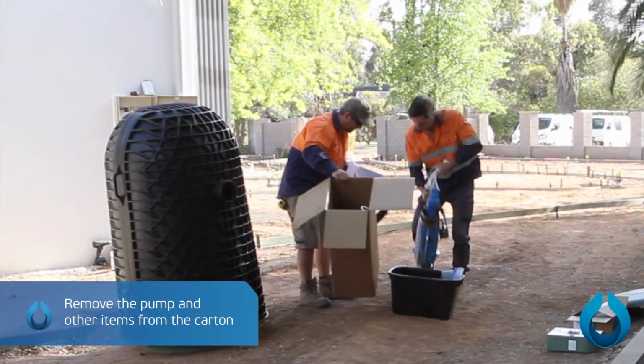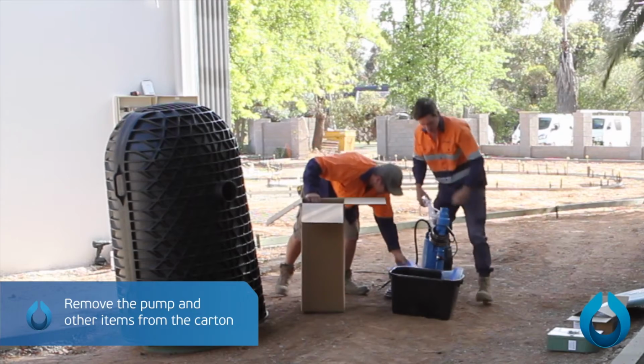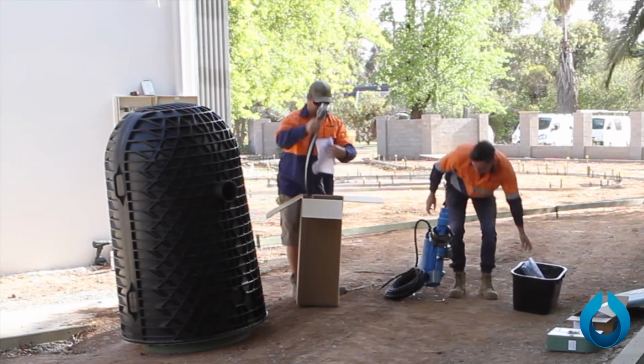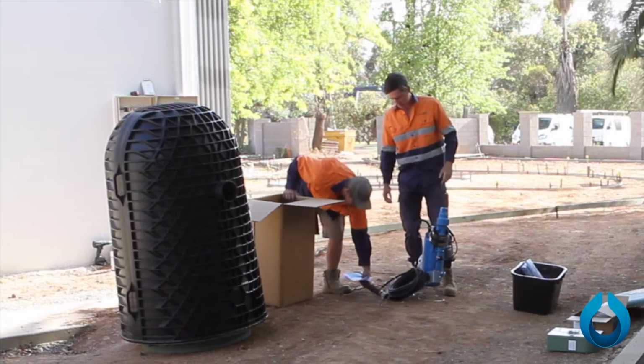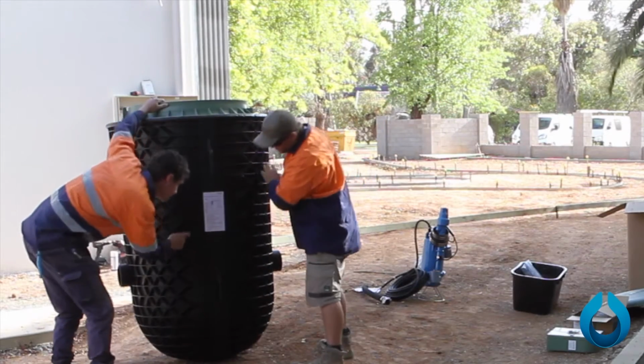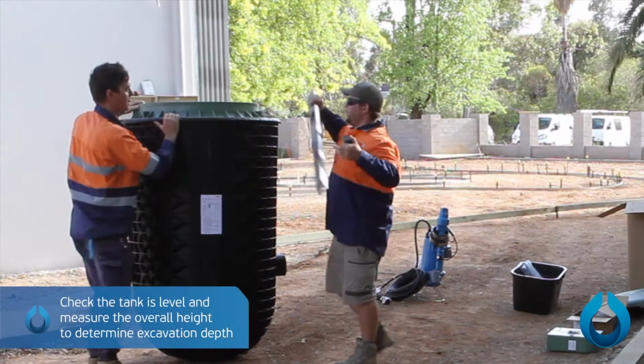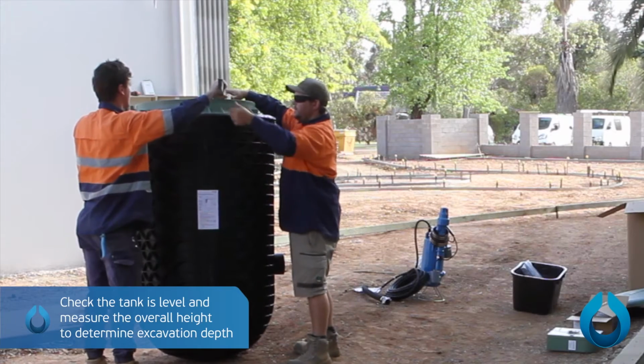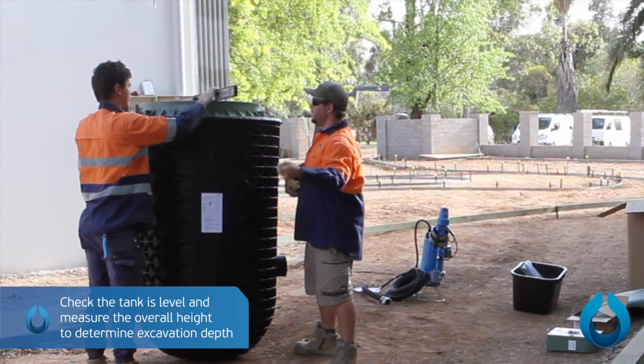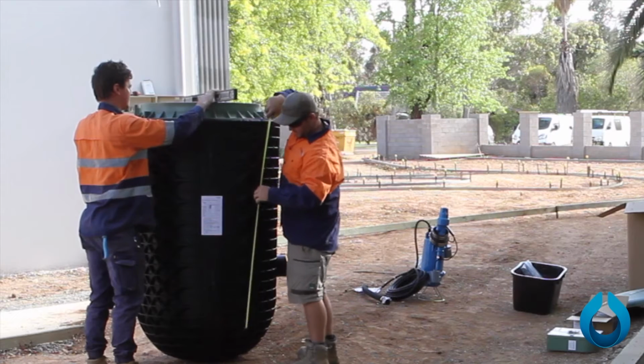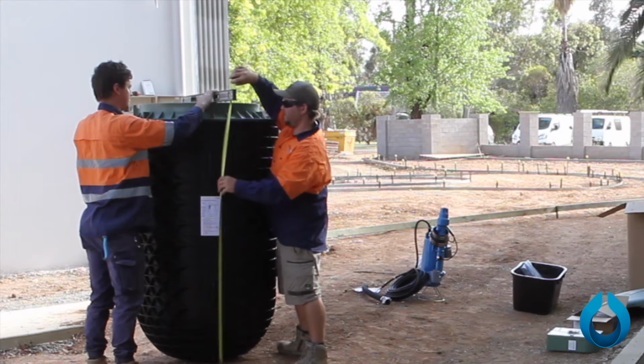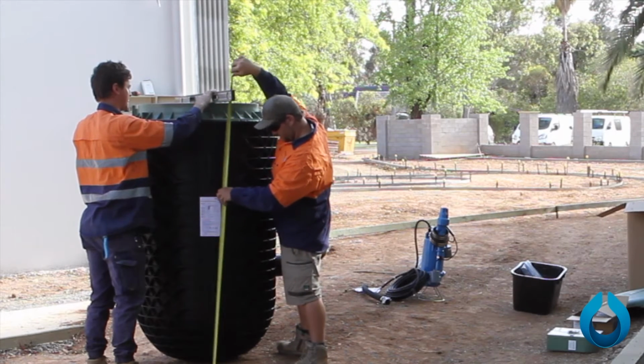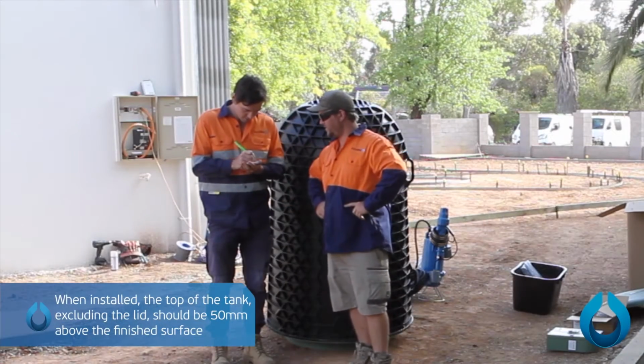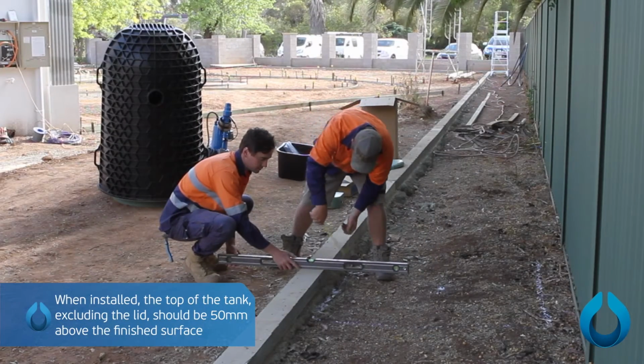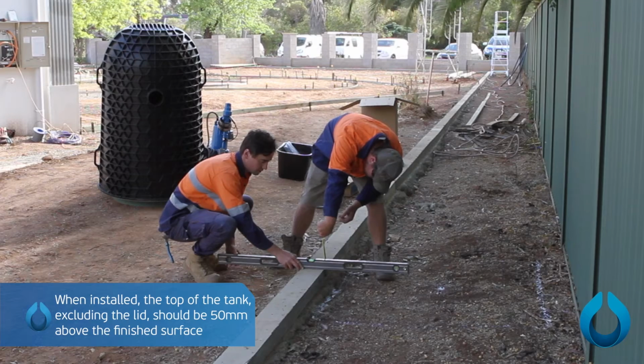Remove the pump and other items from the carton. Check that the tank is level and measure the overall height to determine excavation depth. Please take into account the 100 mm bedding sand requirement and that the lid is to finish 50 mm above the finished surface level.